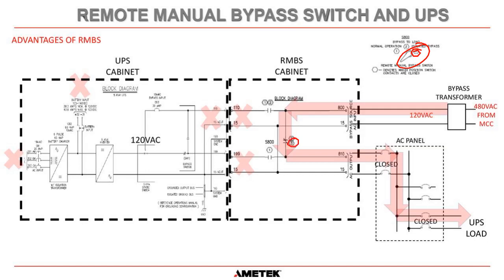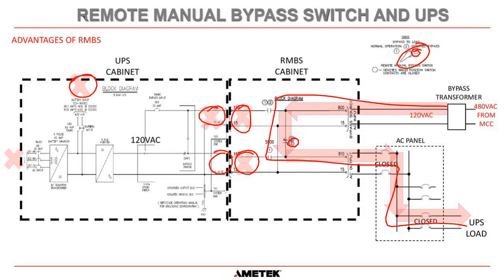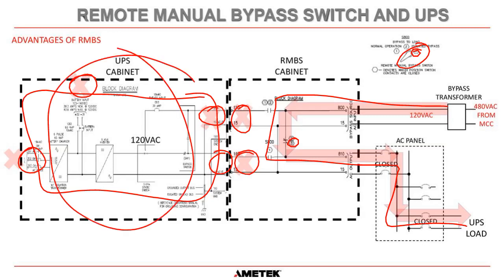position number 3 there, that means power flows down through this way here. And that means this is volt-free. This is volt-free. This is volt-free. This is volt-free. If you turn off the battery and you turn off the MCC, that means everything inside this UPS cabinet is volt-free, and OSHA and NFPA 70E says you are good to go in that UPS, replace capacitors, replace IGBTs, replace SCRs. In truth, replace the whole UPS cabinet if you really, really needed to.